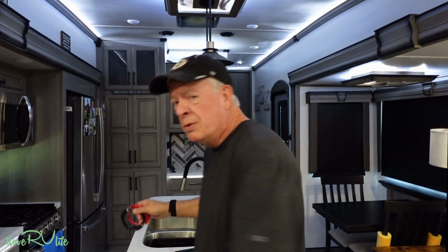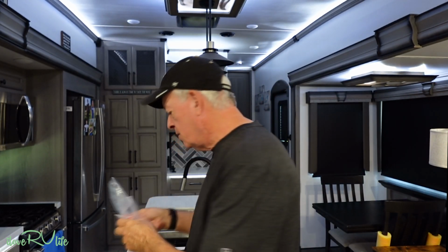It also comes with two small cables, though I don't know their exact size. They're pretty small, and if you're getting into the 15 to 20 amp range, I wouldn't use these. I'd go with something like a 2-aught or 3-aught cable, depending on the length. There are amperage charts, dozens of them, you can use to calculate the right wire size for battery to inverter. But plan for something like a 2-aught or 3-aught cable for a unit like this. They also give you two bags of fuses, which is very nice, you don't typically see that.